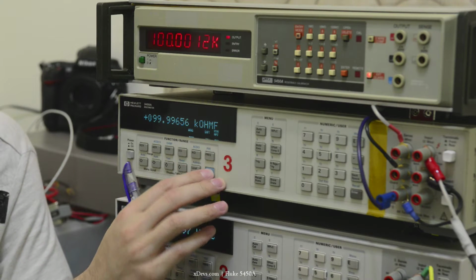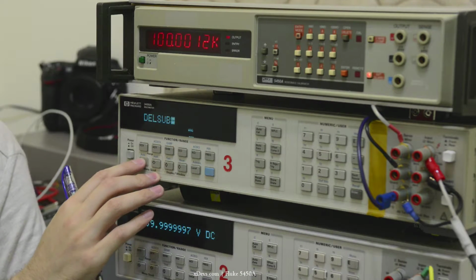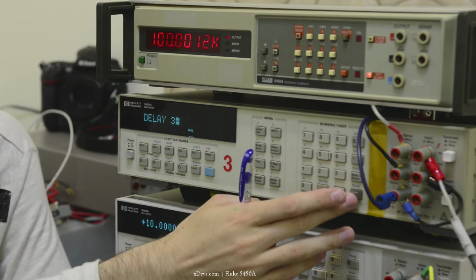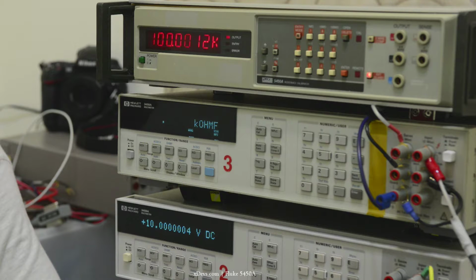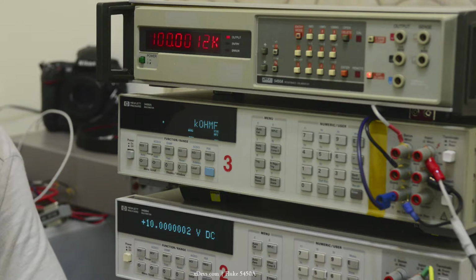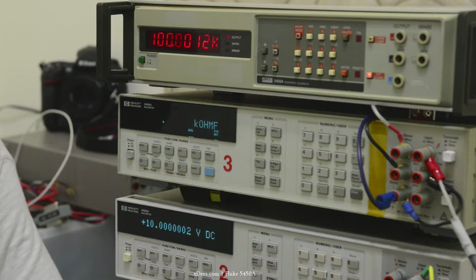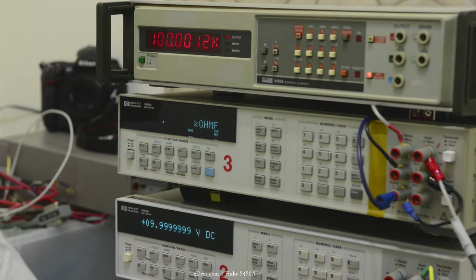What we can try is to enable the delay mode and see if it changes. In theory, if the cable is not impacting our measurement, there should be no change. But the higher the resistance we go, the more sensitive the instrument becomes. The only drawback with the delay is that it takes a while to take each sample, about 14 seconds. So it's not a very quick process, but neither is anything in the metrology area.